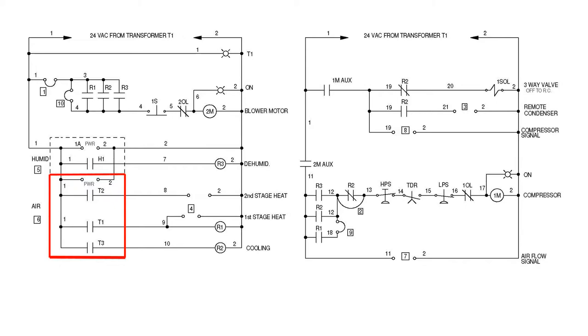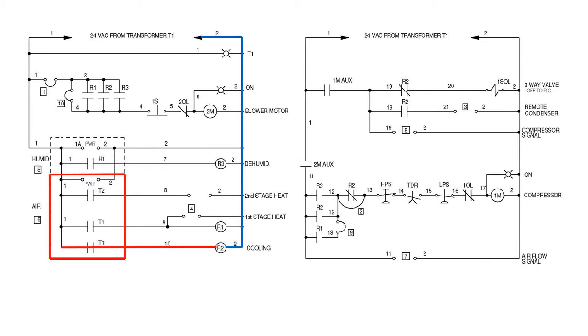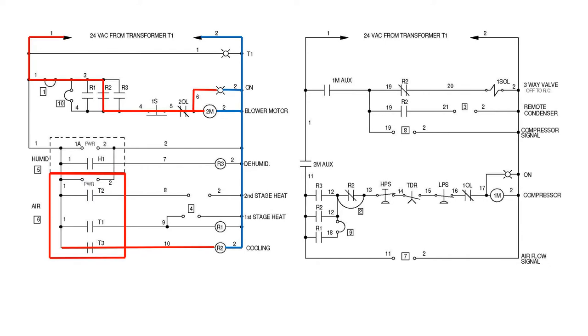The air temperature control is depicted on the left side diagram by the lower portion of the dotted line box. When cooling is required, a normally open relay inside of the controller is energized, sending 24 volts to the coil of the cooling relay located inside of the dehumidifier, here labeled R2. One of the poles on this relay now closes, completing the blower circuit.